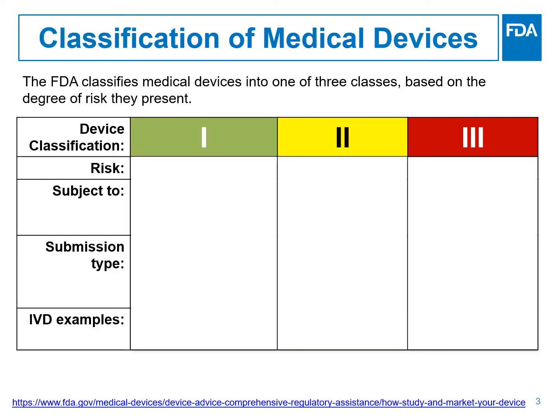The FDA classifies medical devices, including in vitro diagnostics, into one of three classes based on the degree of risk they present and the level of controls that are necessary to assure the safety and effectiveness of the device. Device classification depends on the intended use of the device. The class to which a device is assigned determines, among other things, the type of pre-marketing submission or application required for FDA authorization to market. As device classes increase from Class 1 to Class 3, the regulatory controls also increase.